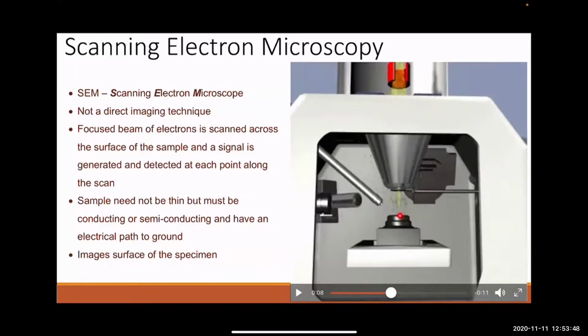So the ultimate probe diameter is going to vary depending on your settings, but the idea is the smaller the probe, the better your imaging resolution. So you can get down to nanometers in probe size. And then as it hits your sample, it's going to scatter, and scattered electrons are going to come out. And then you have various detectors. Here's the Everhart-Thornley detector that will detect what are called secondary electrons, which are electrons that are being emitted from the sample. So they're not the primary beam. The primary beam comes in and kicks off sample electrons, so they call them secondaries. Or this detector here is a backscatter detector, and that is a primary beam detector. So in other words, the primary beam comes in and it can scatter or bounce back.